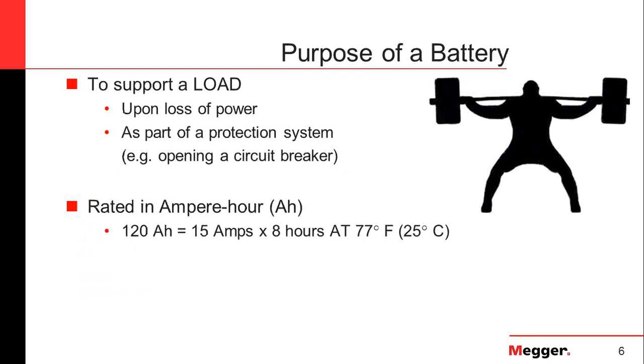The purpose of a battery is obviously to support a load based on a loss of power or as part of a protection system such as opening a circuit breaker. When we look at a battery, we're always provided what kind of load it would support based on a rating of ampere hours. Batteries are rated at a certain amount of current for a specified amount of time. For example, a 120 amp hour battery could be 15 amps by eight hours, and that is at 77 degrees Fahrenheit or 25 degrees Celsius.